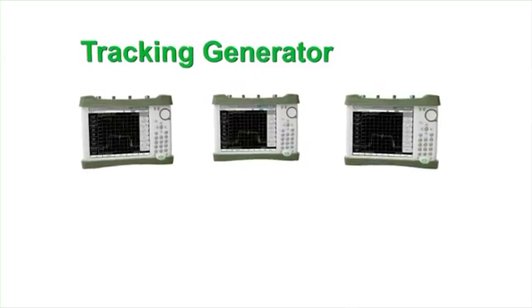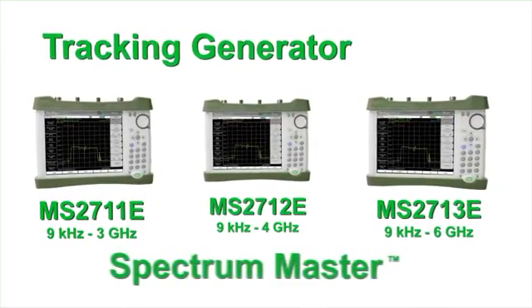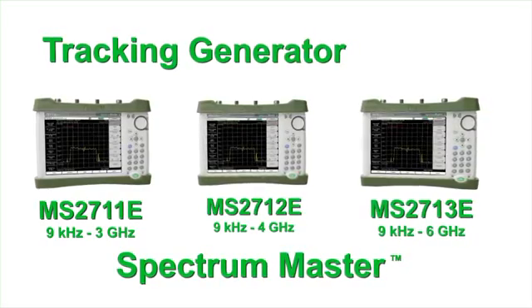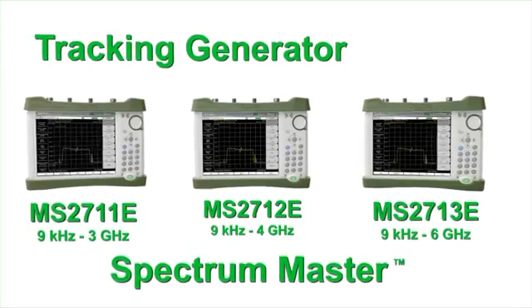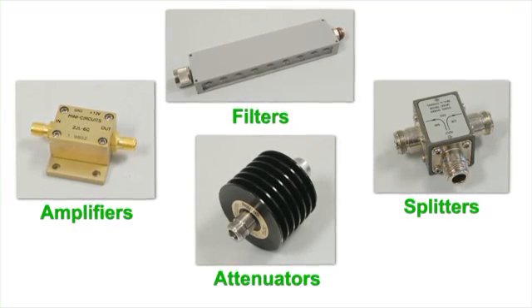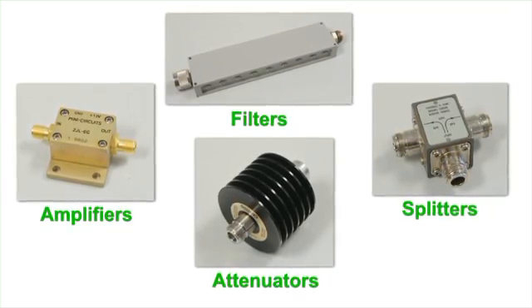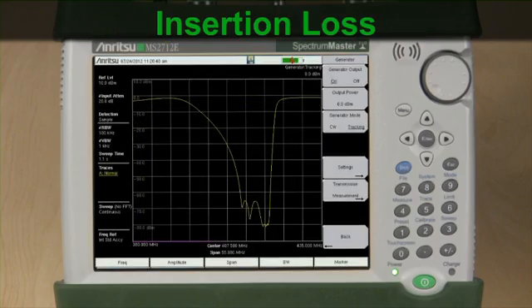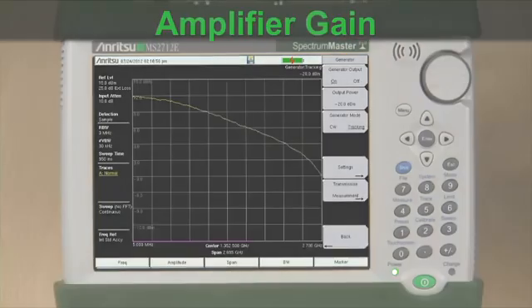Anritsu's tracking generator capability is an available option on the Anritsu E-Series line of Spectrum Master Spectrum Analyzers. The tracking generator helps you characterize the behavior of components and electronic devices, such as amplifiers, filters, splitters, and attenuators, depicting electrical characteristics such as frequency response, insertion loss, and amplifier gain.